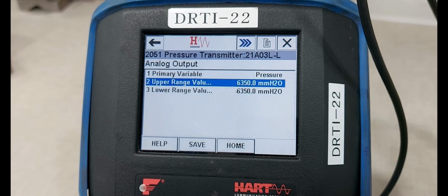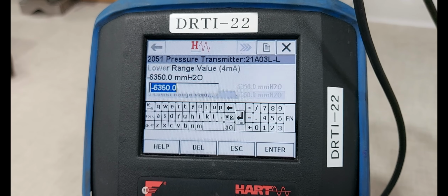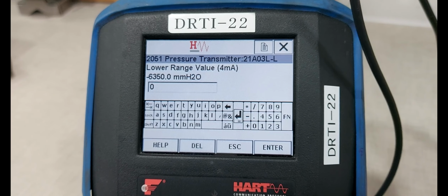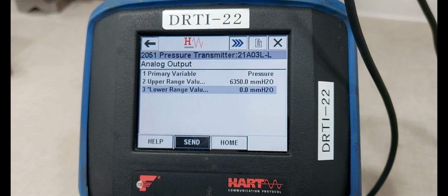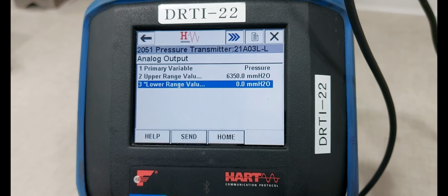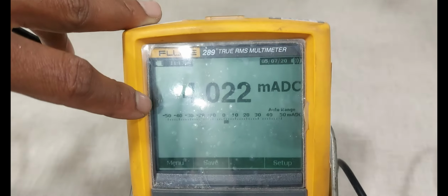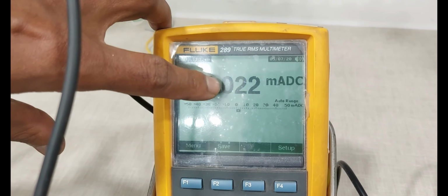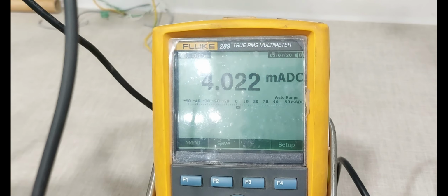Next we select the home menu and select the configuration and the guided setup and select the basic setup and select the analog output area, and first we are changing the LRV. Okay, 0 is LRV value, send it, then OK. Okay, the LRV in the 0 condition. Now output current is showing 4.022 milliamps DC.